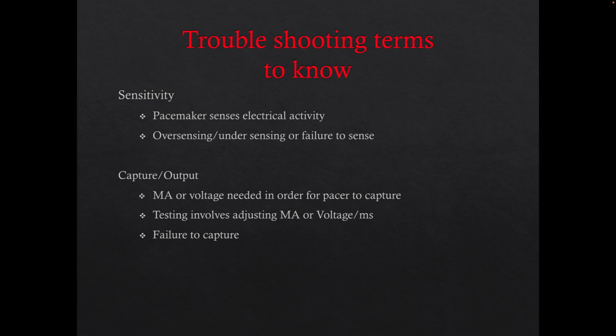Capture and output. Capture means what level of MA do we need, specifically the MA on this, in order for the device to capture. That's what that means. Output is also MA. We use output a lot on this, but you could use that term here. Capture is probably the more common word, but I wanted to use both in case you ever hear people say what's the output or capture on the device. So we have MA or voltage that's needed in order for the pacer to capture, like I mentioned. Testing involves adjusting your MA or your voltage. Voltage is on this, MA is on this. And then we talked about failure to capture and what to do. So we're going to go over that.